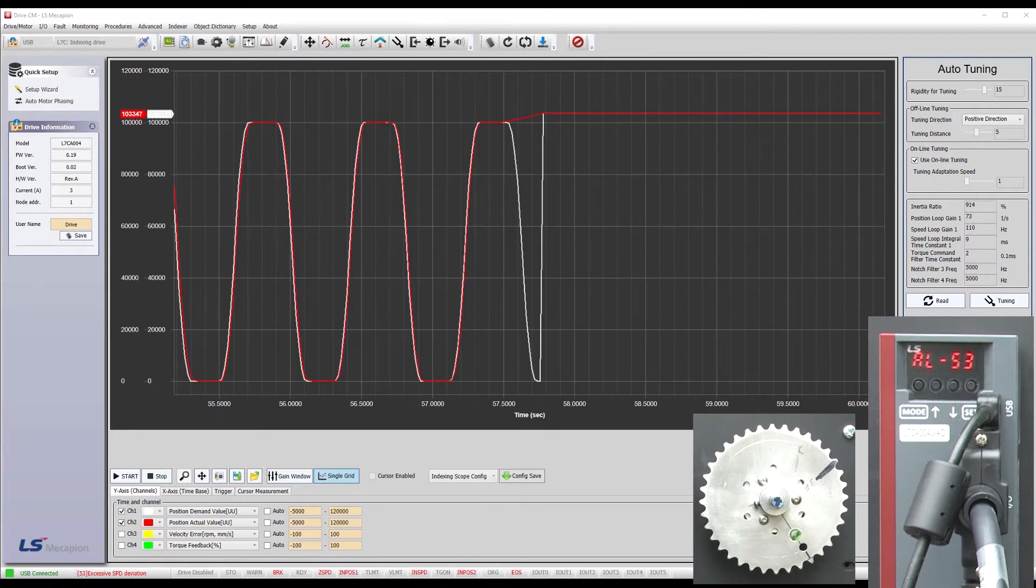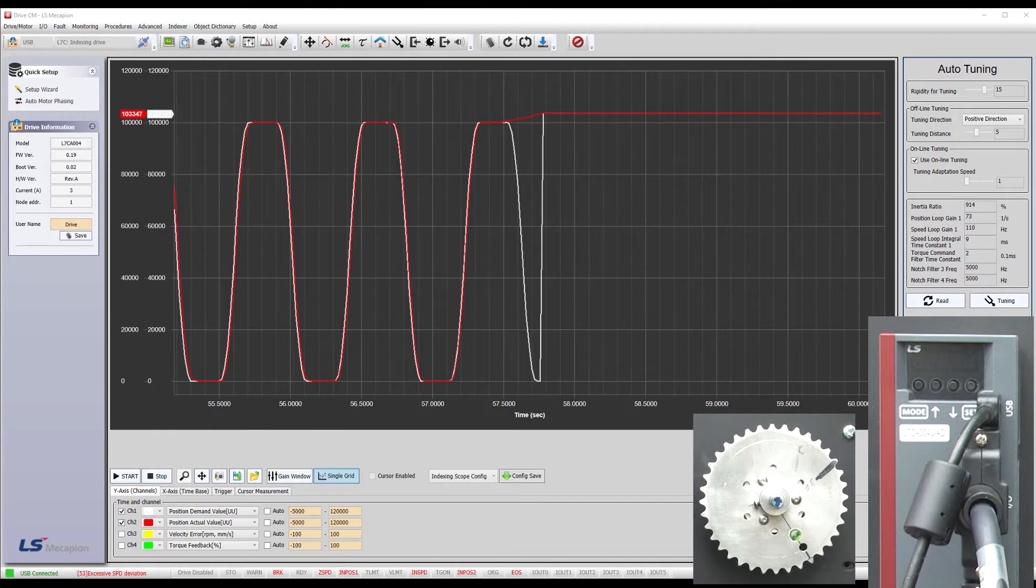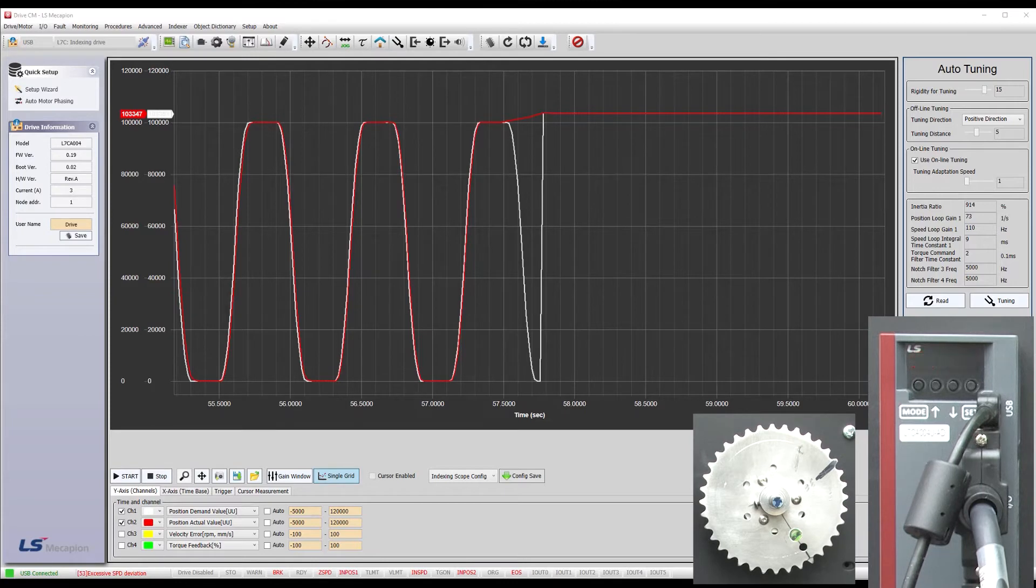So, be careful you don't overdo tuning. You can get it to the point where it becomes unstable. I would even suggest going until it fails like this, if your system allows it of course, and then back off a few rigidity steps so you know you have margin before things go unstable.